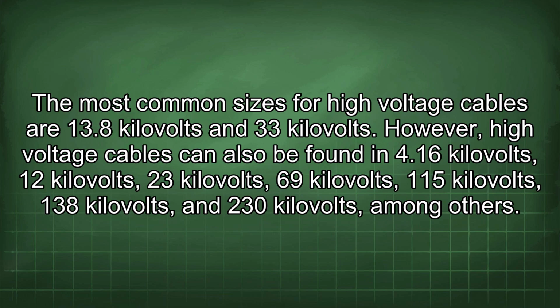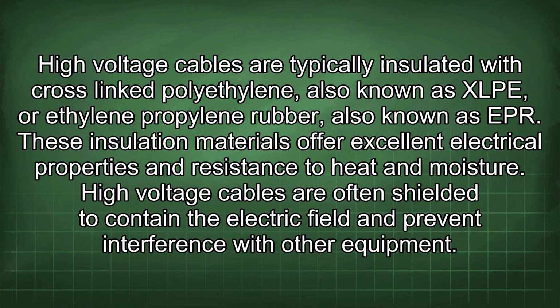The most common sizes for high voltage cables are 13.8 kilovolts and 33 kilovolts. However, high voltage cables can also be found in 4.16 kilovolts, 12 kilovolts, 23 kilovolts, 69 kilovolts, 115 kilovolts, 138 kilovolts, and 230 kilovolts, among others. High voltage cables are typically insulated with cross-linked polyethylene, also known as XLPE, or ethylene propylene rubber, also known as EPR. These insulation materials offer excellent electrical properties and resistance to heat and moisture.